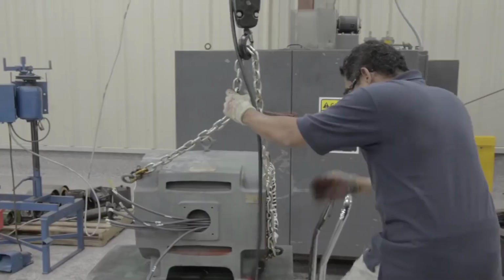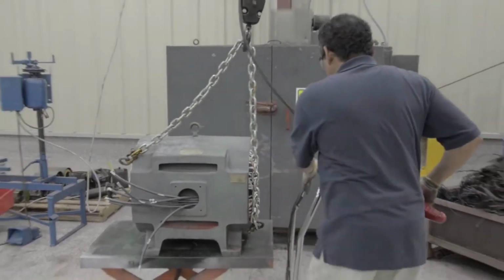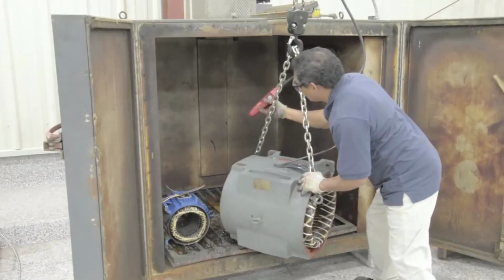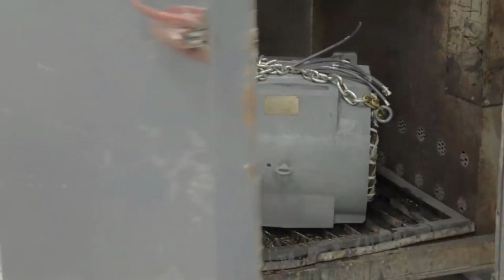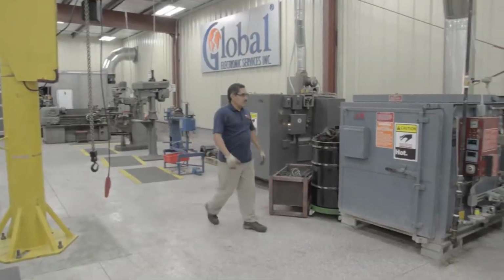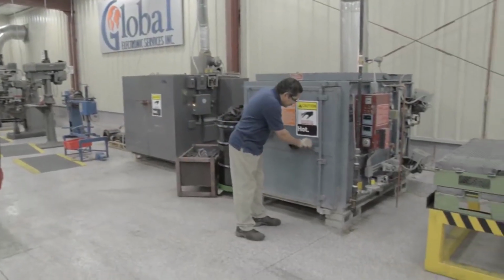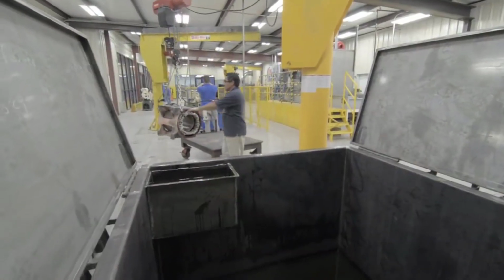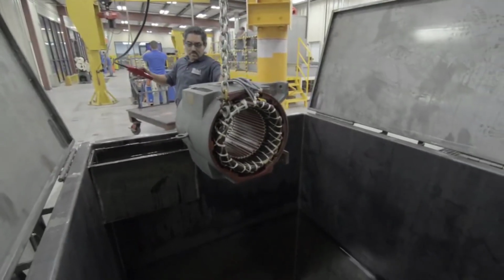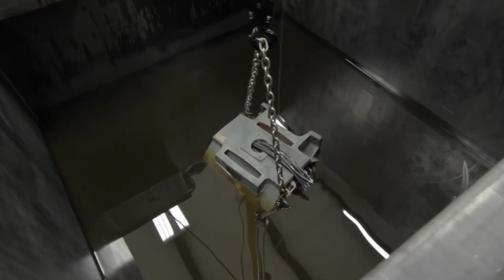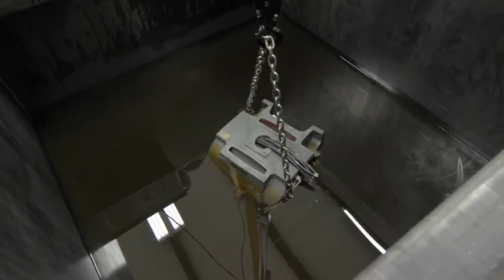The stator is heated to 90 to 120 to remove any internal moisture and improve varnish bonding to the coils. It is then dipped in a special varnish treatment. The varnish bonds the windings together and prevents the coil movement within the stator core.